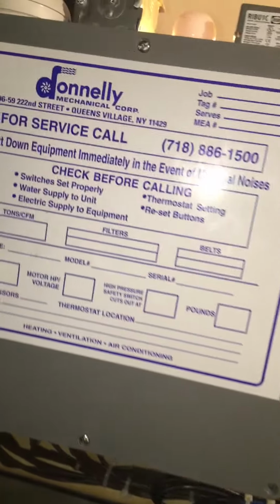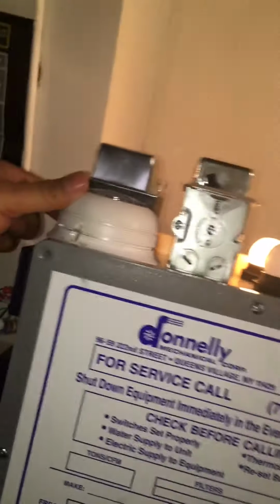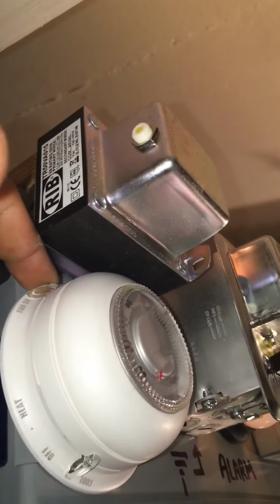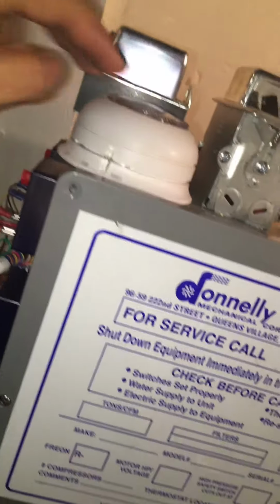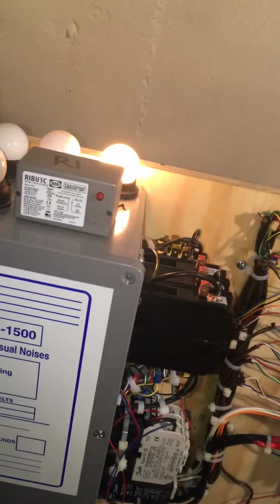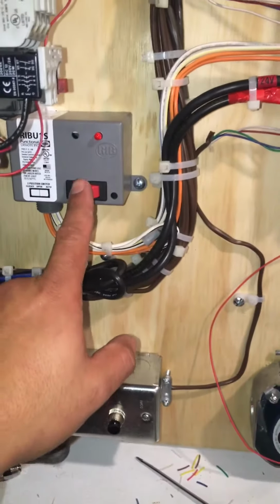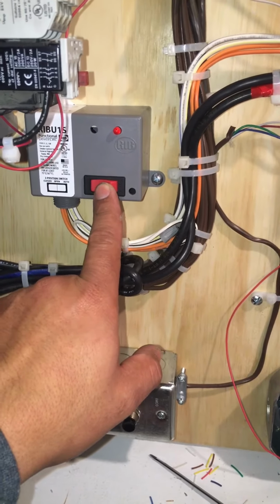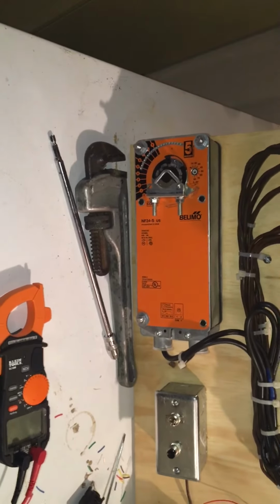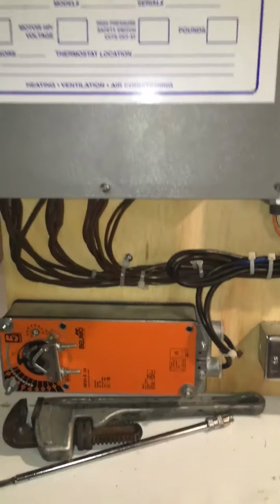And if we put the cooling into auto, we put the fan into auto over here, which is right there, and then if I raise the set point, there we go. Everything is starting to click off. The only thing on is the condenser water pump, and that's because I have it on by the HOA switch. But if I kick this off, everything's off. Belimo's doing its thing. And that's all she wrote.